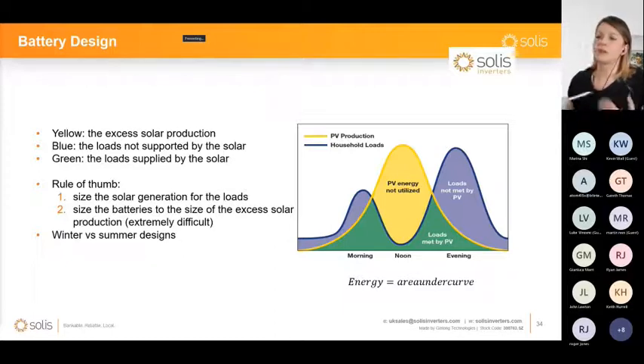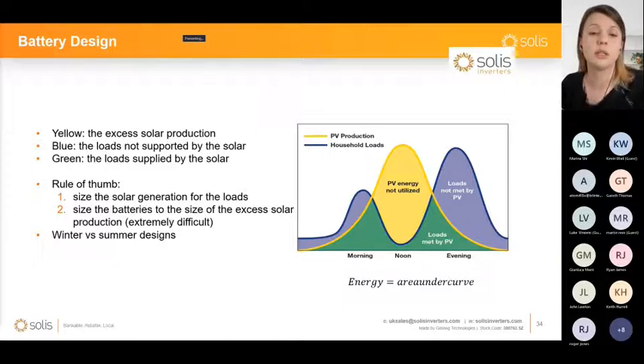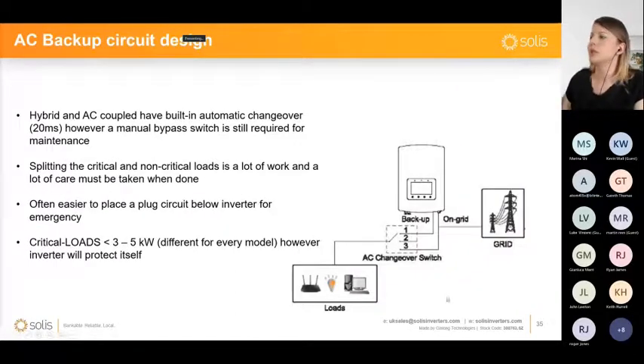So the summer design would be based on the PV that's going to be available during the summer, when it's higher. Wintertime, of course, you're going to have some really dull days where you might have no PV available whatsoever. So you need some extra storage in order to cover some of that consumption.